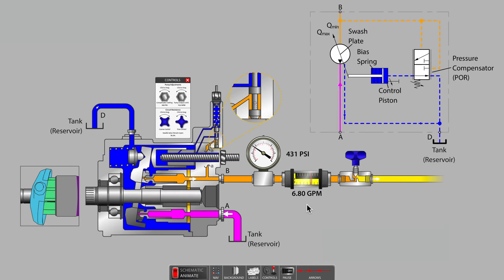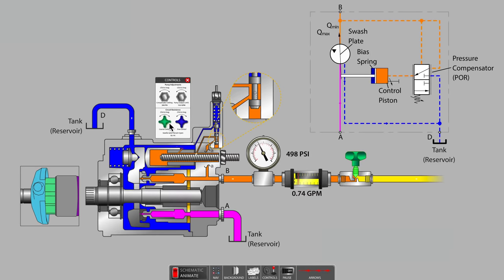Remember, we started out with 10 gallons per minute. As we continue to tighten the needle valve, we eventually arrive at a circuit pressure of 500 psi and we find out that the flow meter now indicates zero flow.